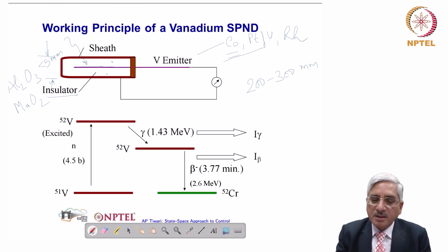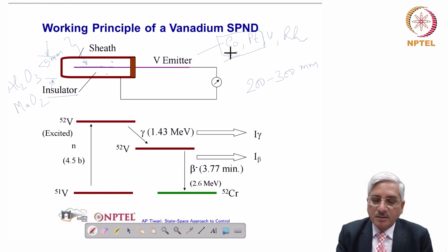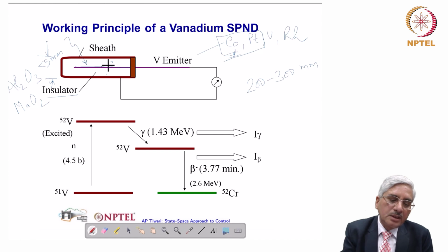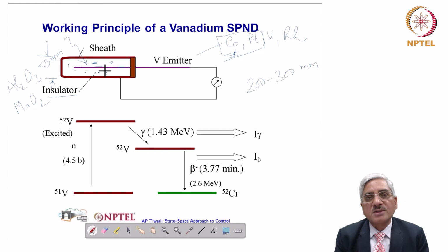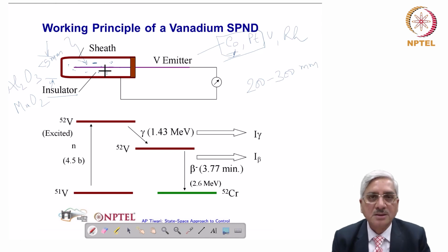Cobalt and platinum detectors operate on the first one: their nucleus will absorb a neutron and release a gamma, which is equivalent to a photon, and that photon will do photoelectric effect, pair production and Compton effect in the insulator material, and all these three phenomena give rise to electrons.